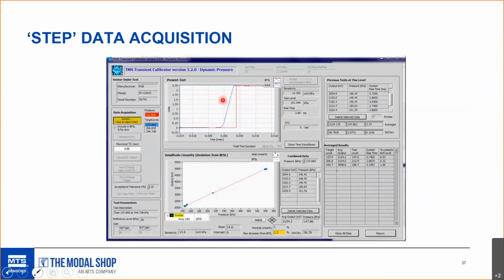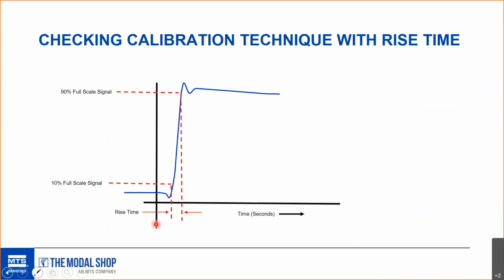This is the rise in pressure in the blue curve that we saw. This is the gas expanding into the small volume and hitting the diaphragm of the sensor under test. And we collect the statistical data down here to show the linear relationship. It looks like a complex software interface, but we do things in the software, and primarily we measure the rise time. The operator checks his data, because if he has a bad rise time, he can detect it in the software, and we can reject that data in case there's been an operator error.